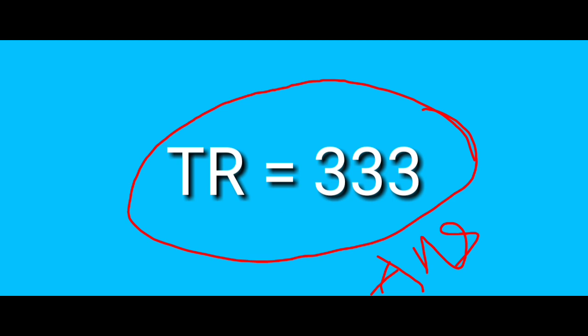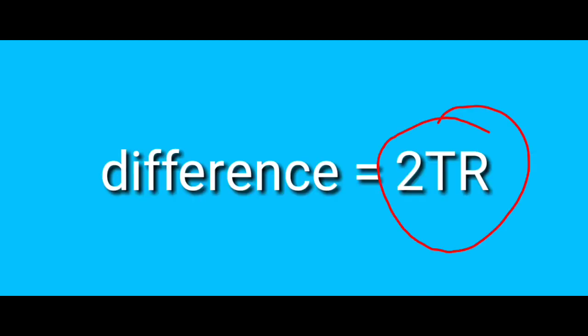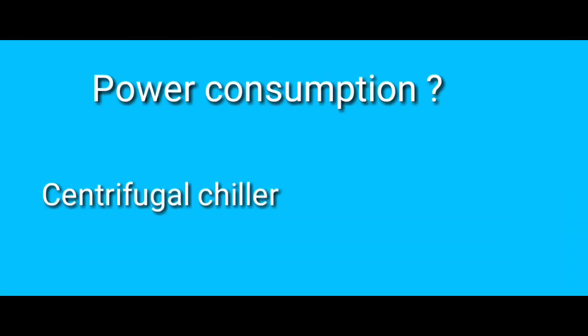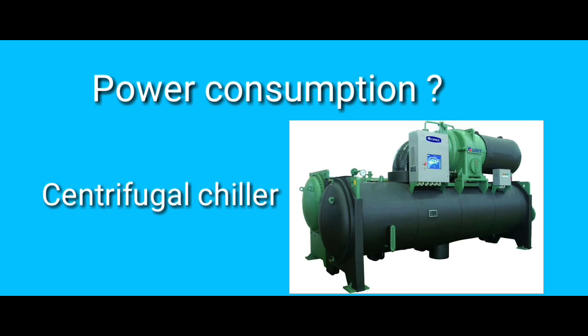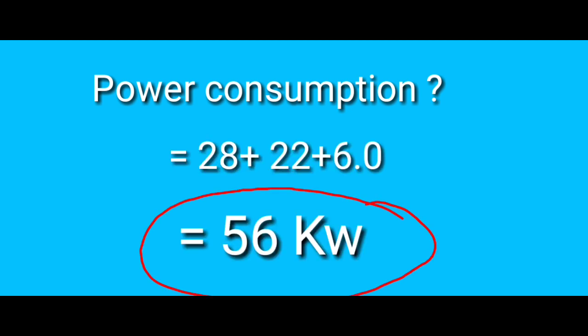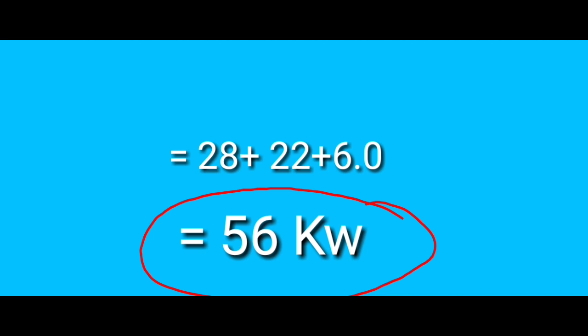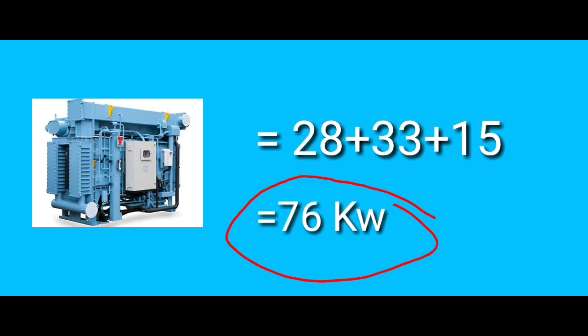We are going to find out the auxiliary power consumption for centrifugal chillers. That power is equal to 28 plus 22 plus 6.0, which equals 56 kW. When you see the power consumption, it is equal to 76 kW — same TR rating with a maximum 2 TR variation, but power consumption difference is 20 kW.